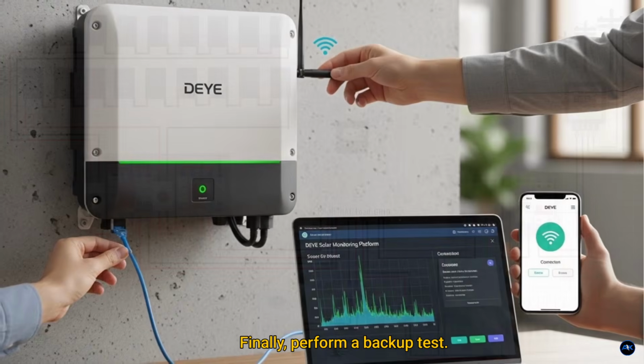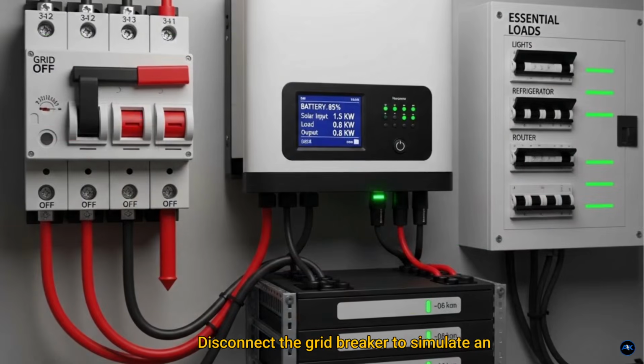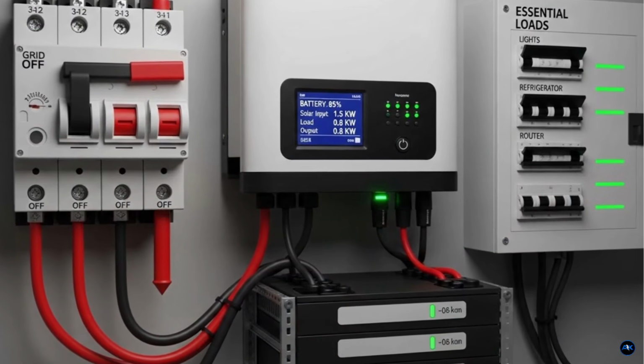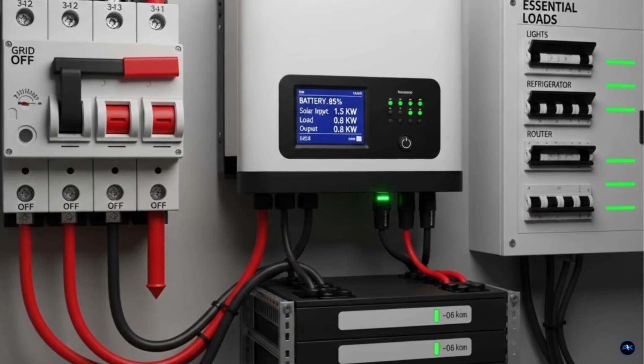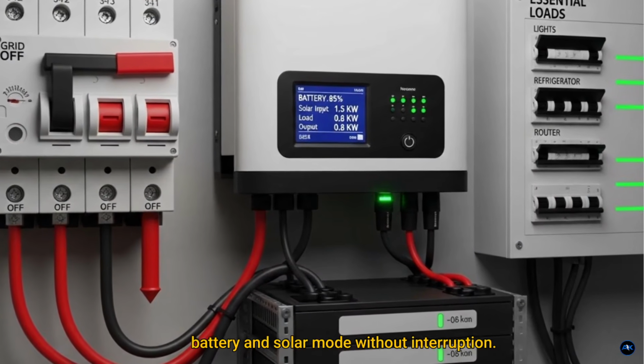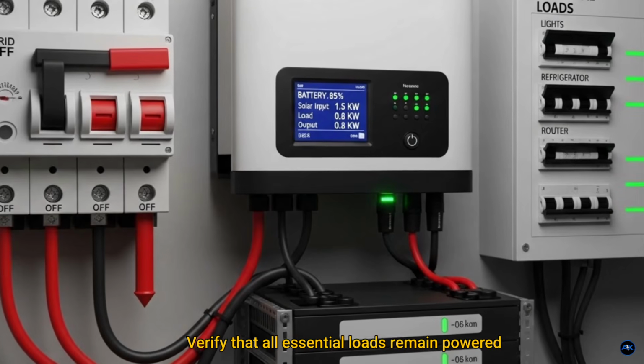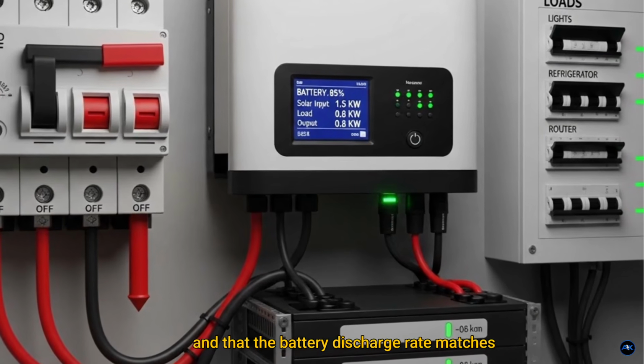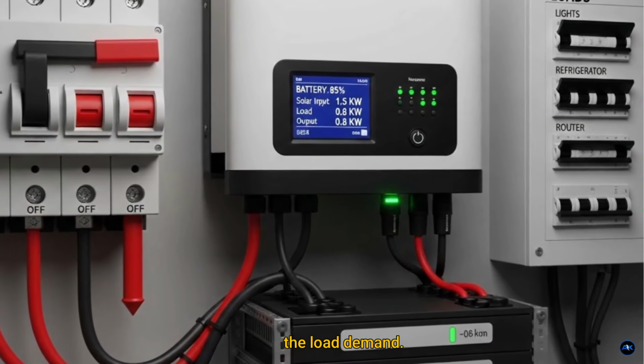Finally, perform a backup test. Disconnect the grid breaker to simulate an outage. The inverter should instantly switch to battery and solar mode without interruption. Verify that all essential loads remain powered and that the battery discharge rate matches the load demand.